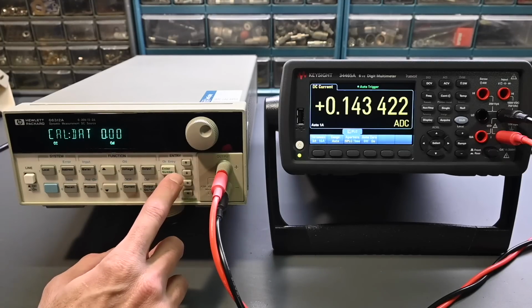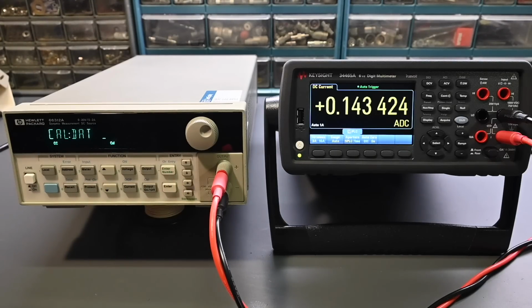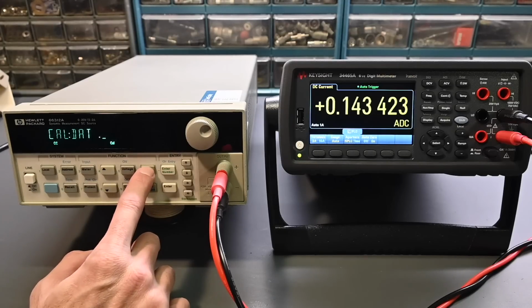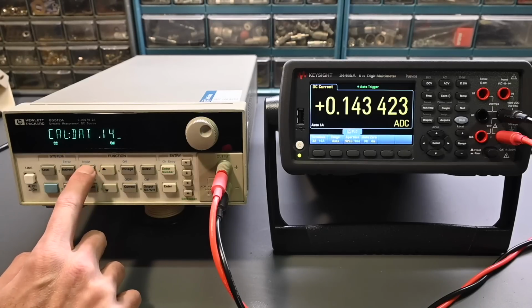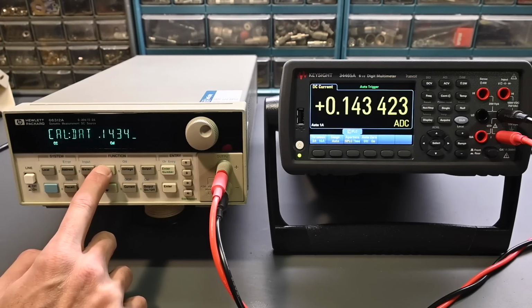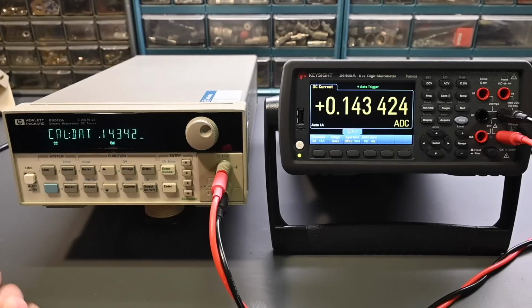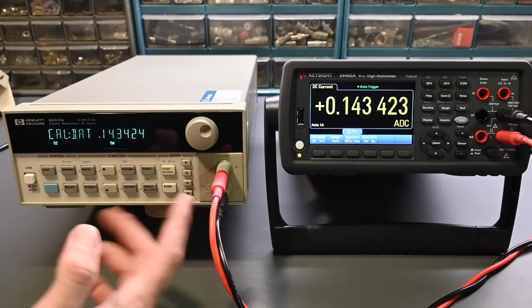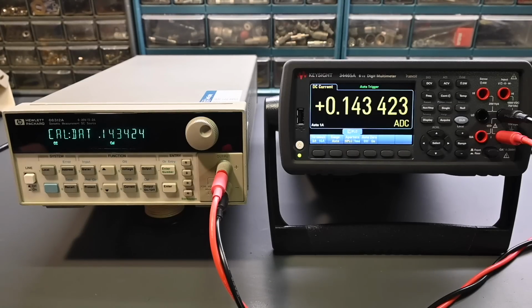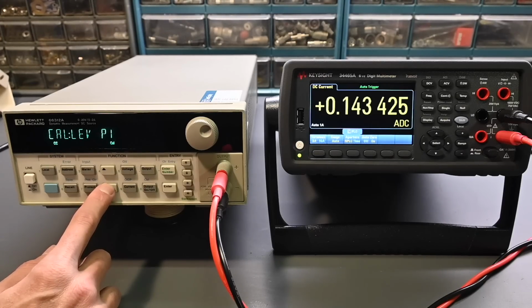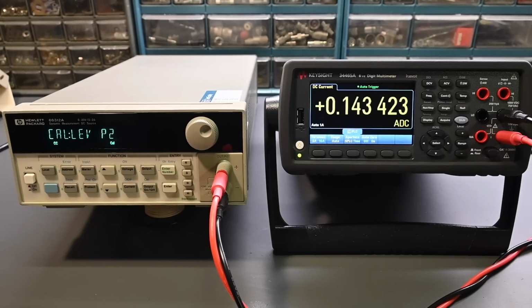So now for here, we're going to press enter number and enter the value. We have over there, it's in amps DC. So just start with the decimal point. 1, 4, 3, 4, 2, a little bit of fluctuation on the last digit. Looks like it's probably about, maybe about 4. Go with 4. That should be fine. Okay, so enter. It says press Shift Cal. Scroll to cal level. Down arrow again. Second point. Press enter.